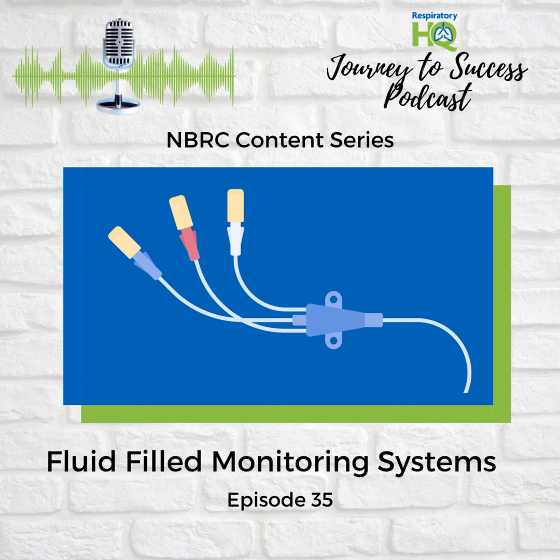Inside the transducer, there's a diaphragm that's sensitive to pressure. It's enclosed in a dome filled with fluid. When the patient's heart beats, those pressure changes travel through the fluid and hit that diaphragm, causing it to move. And that movement creates a tiny electrical signal. Got it. So we've got this tiny signal. What happens to it next? Well, that's where the amplifier comes in. It takes that weak signal, boosts it to a level that's clinically useful, and filters out any noise along the way. Then that amplified signal goes to a monitor, which shows you the pressure waveform in real time, and often also to a recorder that documents it for later analysis.